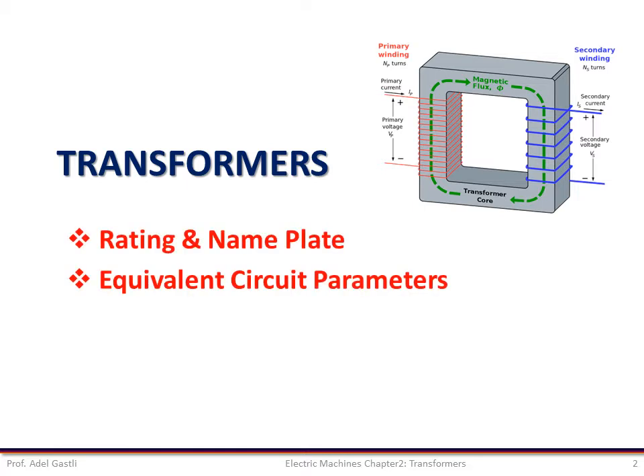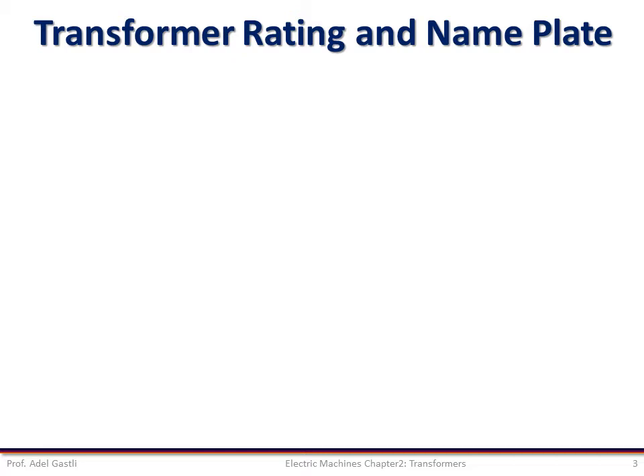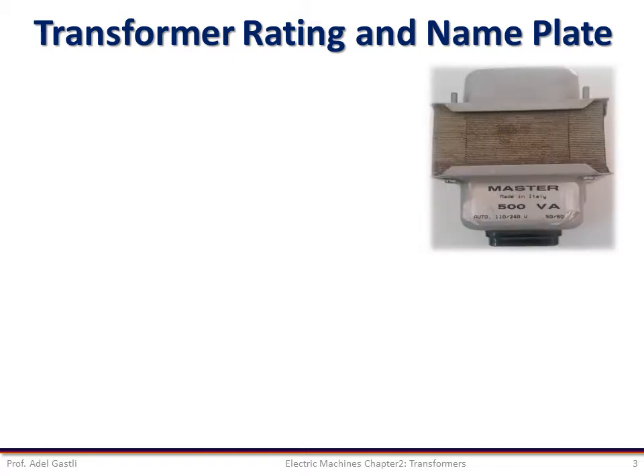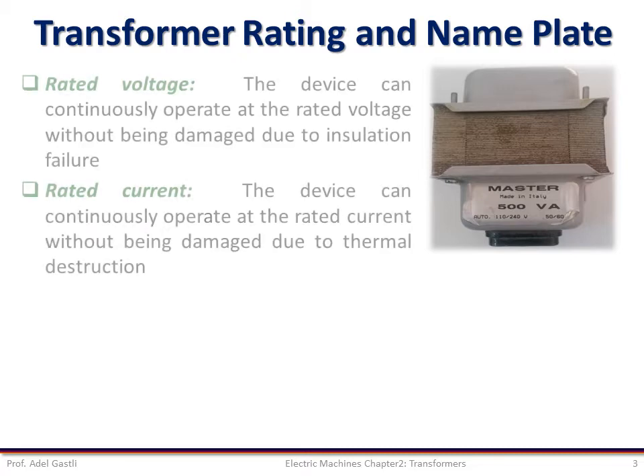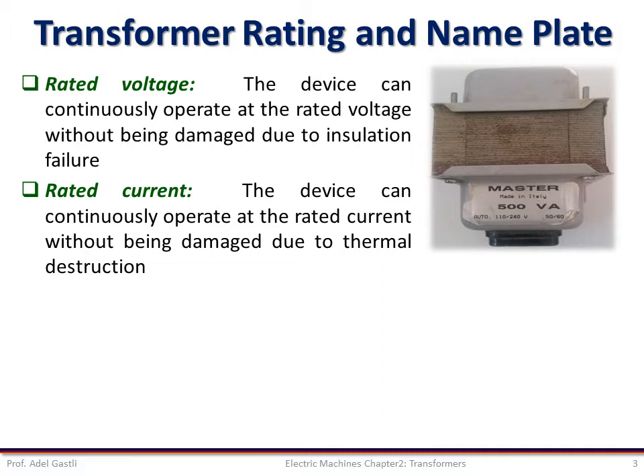Rating and nameplate and the equivalent circuit parameters. Every transformer is designed and constructed for a specific application and ratings. The ratings are usually provided and displayed on a nameplate that is fixed on the transformer casing. The ratings of a transformer are its rated voltage, which means the device can continuously operate at the rated voltage without being damaged due to insulation failure, and the rated current, which means the device can continuously operate at the rated current without being damaged due to thermal destruction.